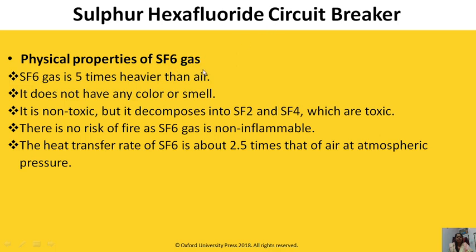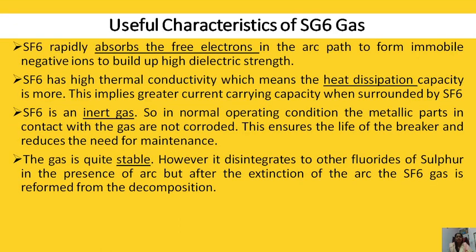Some physical properties of SF6 gas: SF6 gas is 5 times heavier than air. It does not have any color, smell, or odor. It is non-toxic, but when it decomposes into SF2 and SF4, these two are toxic. There is no risk of fire as SF6 gas is non-inflammable. The heat transfer rate of SF6 is about 2.5 times that of air at atmospheric pressure. These are some useful characteristics of SF6 gas, because of which the SF6 circuit breaker is preferred over ABCBs and OCBs.